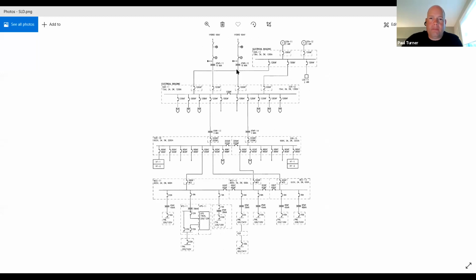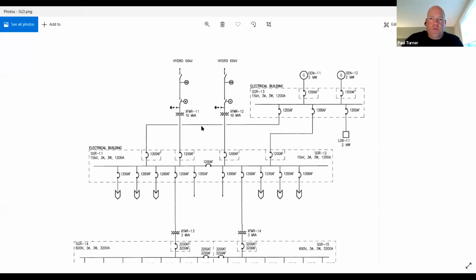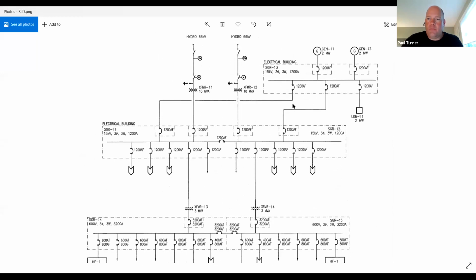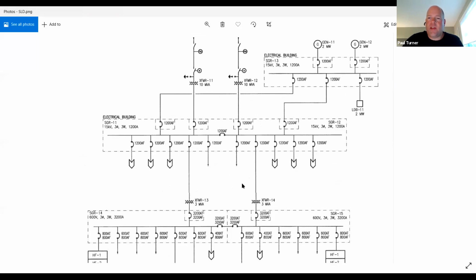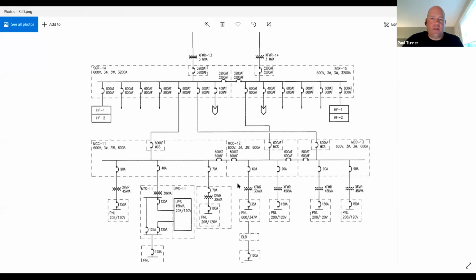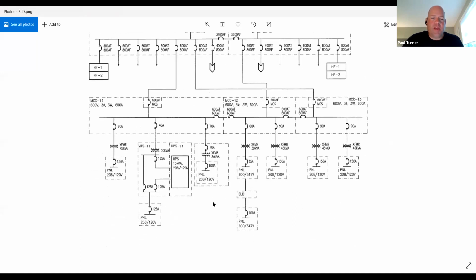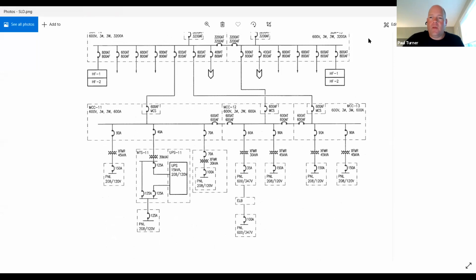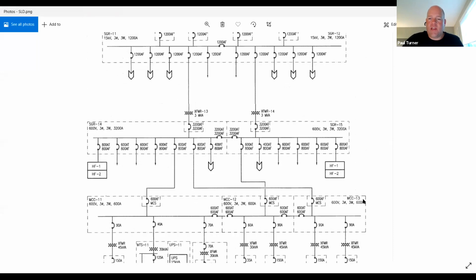Okay, so hopefully you can see the diagram that's up on the screen here. This is an electrical distribution system, dual redundant, fed off of a 66 kV utility feed from the local utility. All components are redundant and backed up with a diesel genset and UPS systems downstream. We've got a switchgear, MCCs, and panel systems.